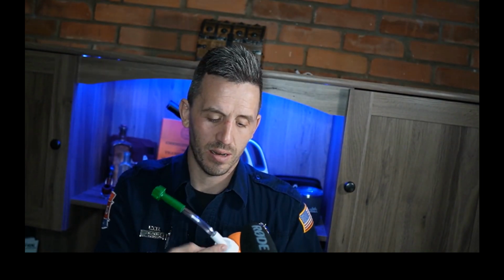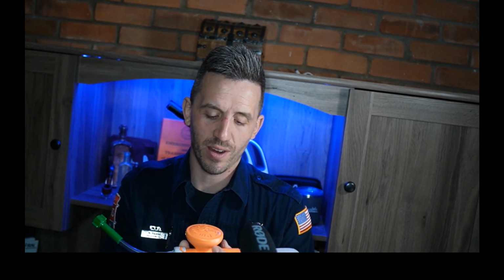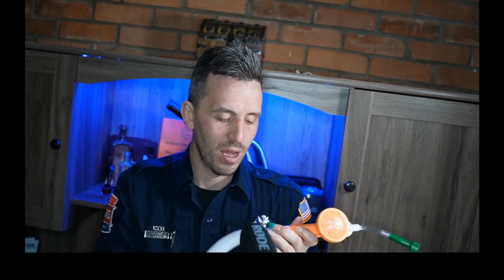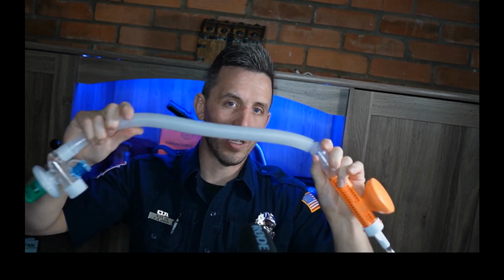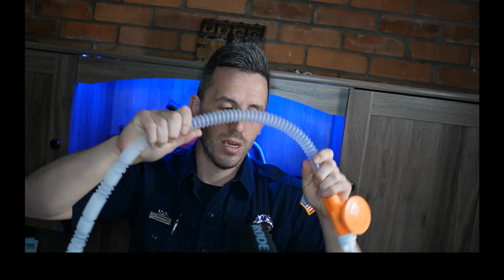Now, this piece right here does allow for some FiO2 adjustment if you have that from the manufacturer. Granted, we don't. Ours only provides 30%. This little orange piece mixes the supplied oxygen with the ambient air and has a viral and bacterial filter in it. You need to make sure that this does not become occluded during the course of its use. So don't allow this to just lay on the bed and then get covered by the sheet or something like that. The corrugated tubing ideally needs to be stretched completely out all the way, not just part of the way, but completely all the way out. That will keep it so that it doesn't get any kinks or tug on your patient's face.